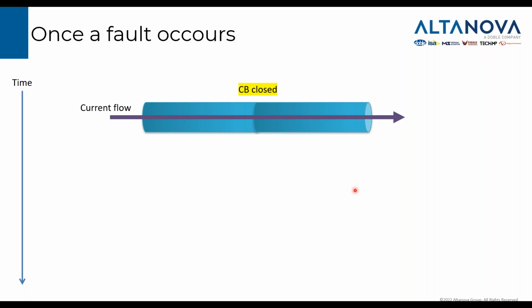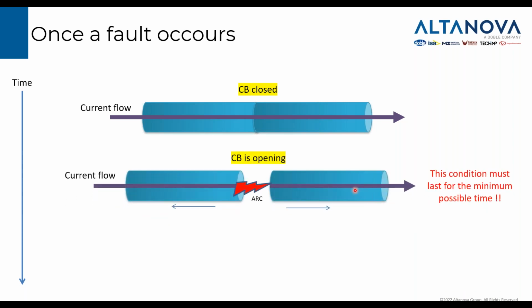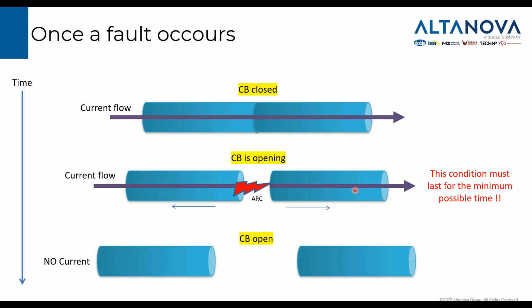If we look inside the circuit breaker, we have to imagine that the current is flowing through metallic parts that touch each other. In this way we say that the circuit breaker is closed. But when the open command is issued, the two metallic parts start to separate, and when this operation starts, there is an arc flowing from one part to another, and this condition must last for the minimum possible time. When the two metallic parts are well separated, the arc is not present anymore, so the current flow is interrupted.